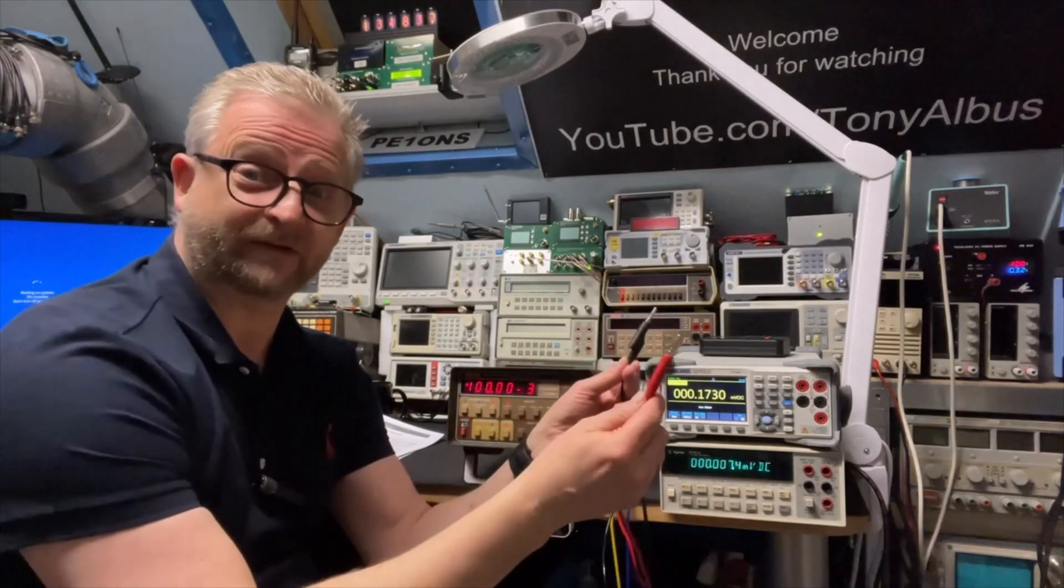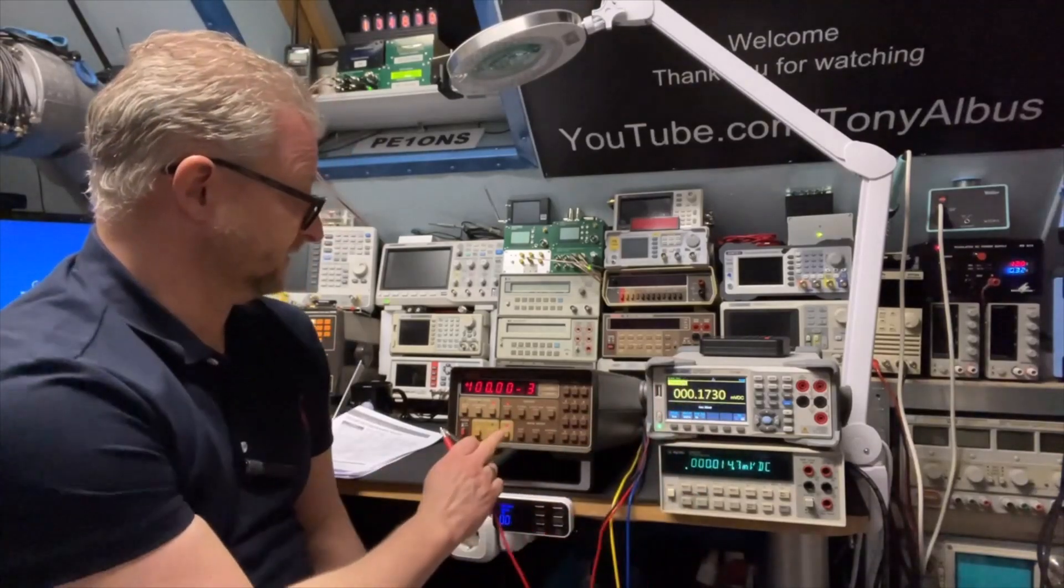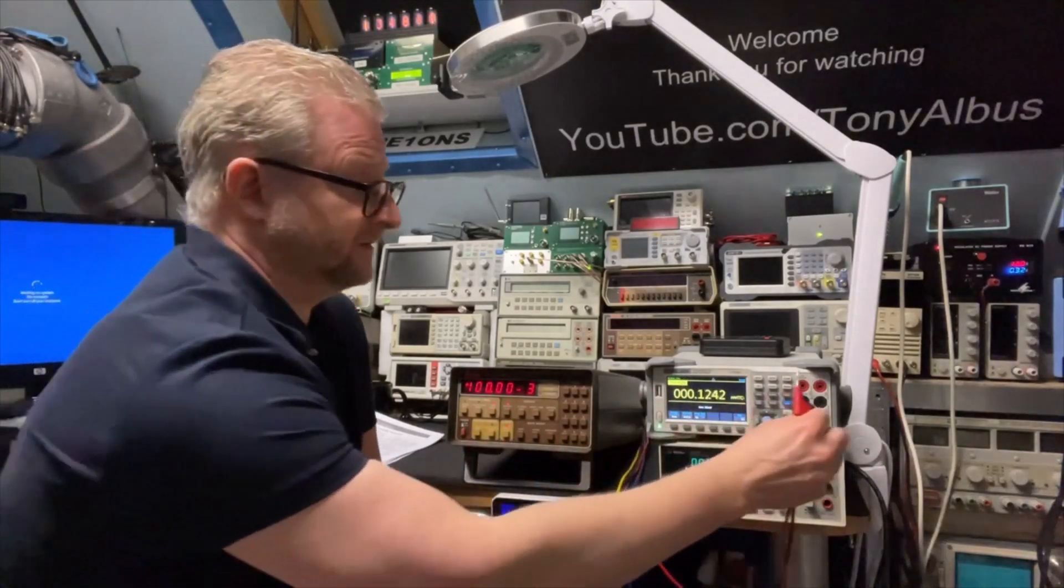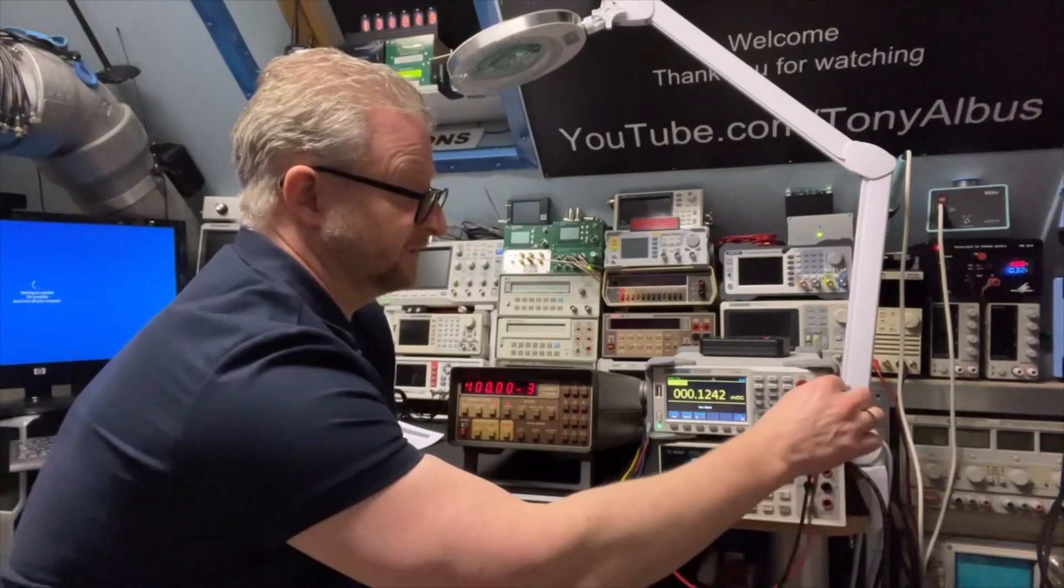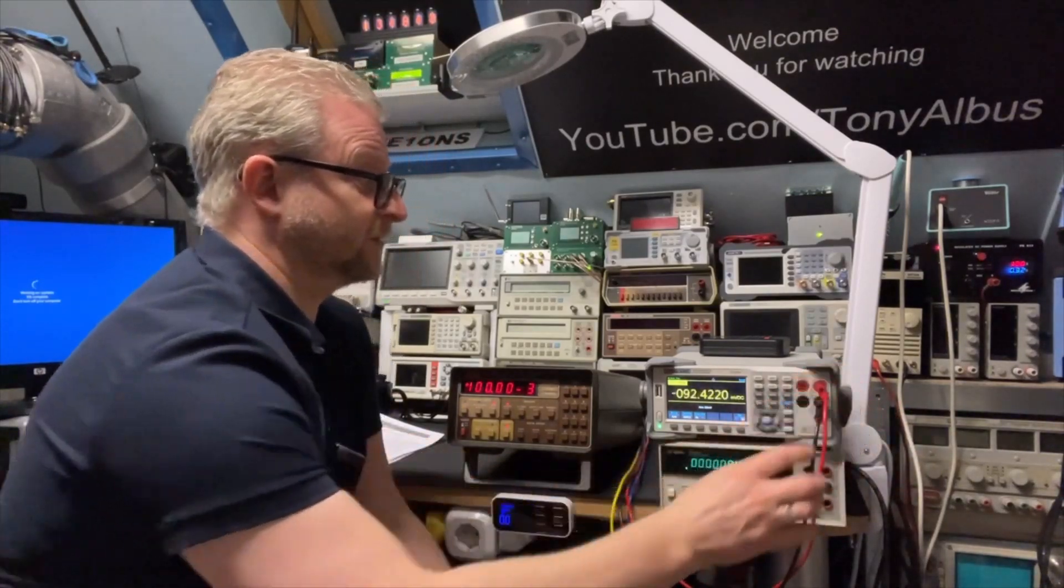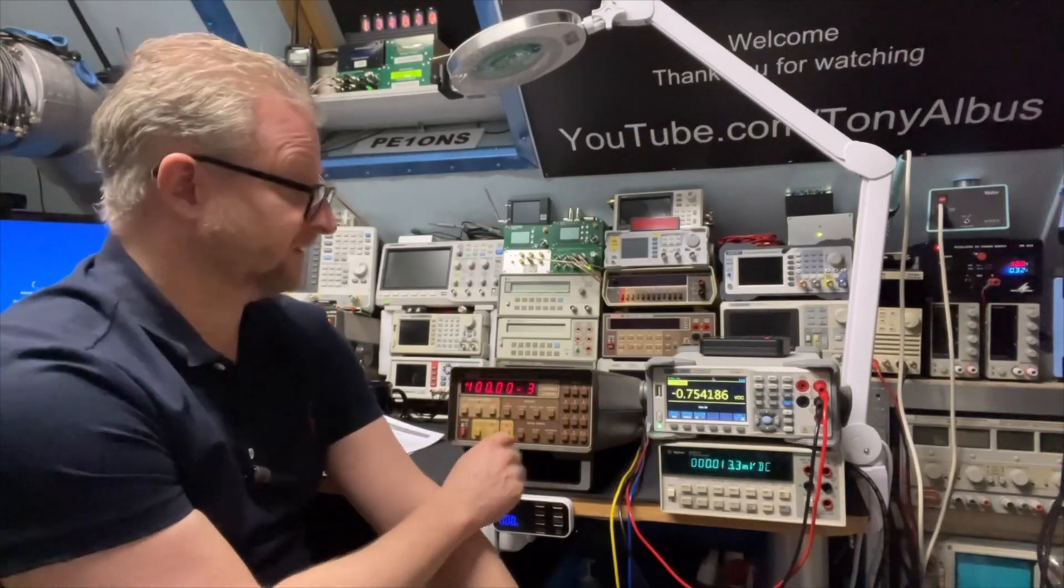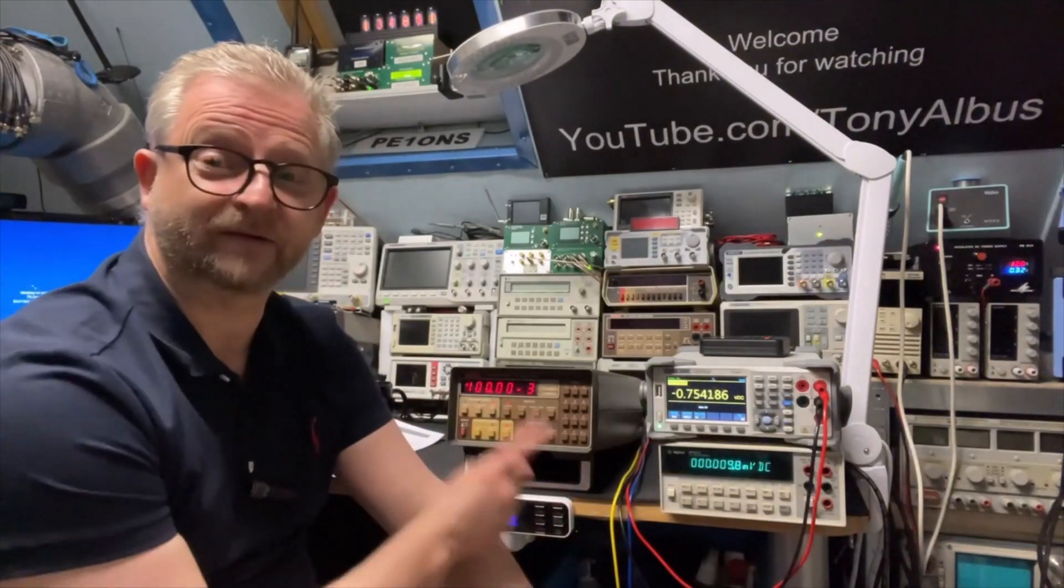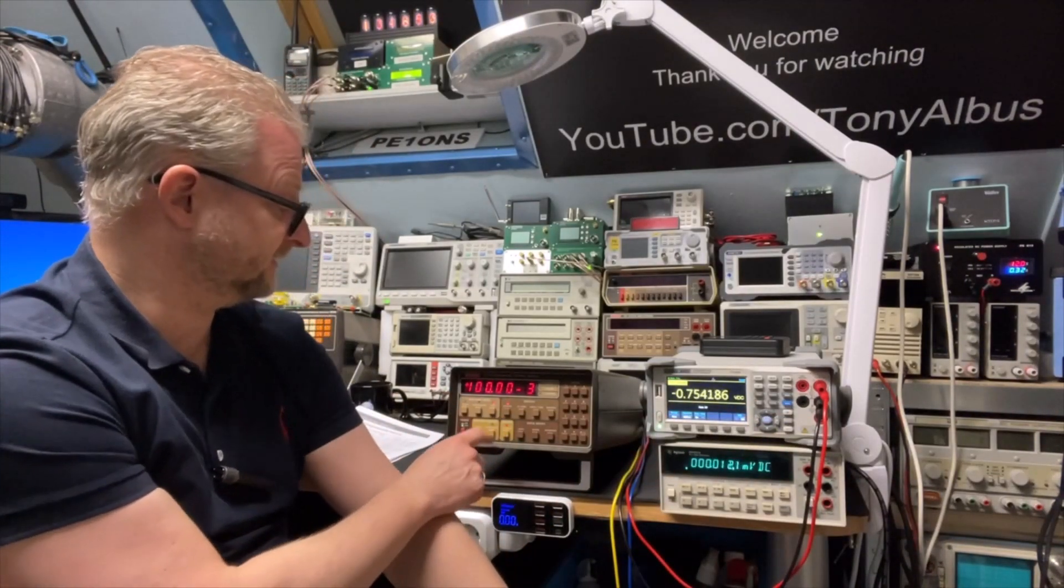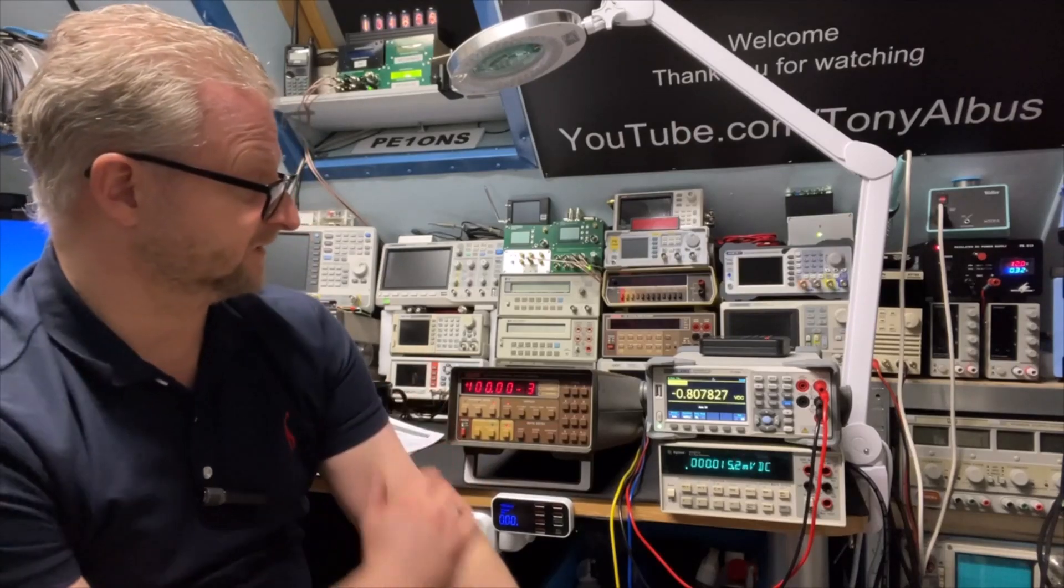Let's turn it around and connect it to the voltage meter. So how are we connected? Try first without the sense wires. Don't forget to switch the output to on depending on the voltage. If you are working with the high voltage, you probably first want to connect your wires before you switch on the output.